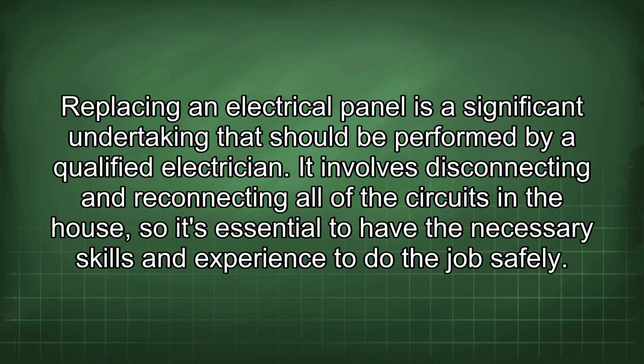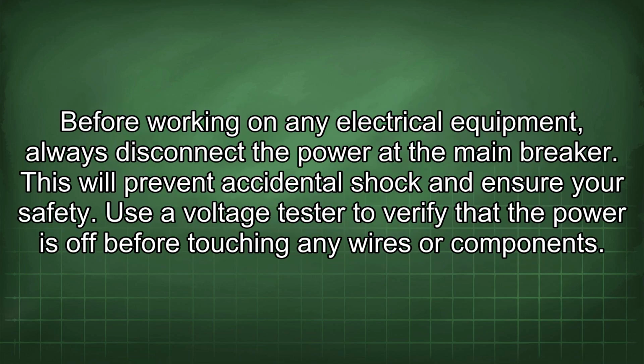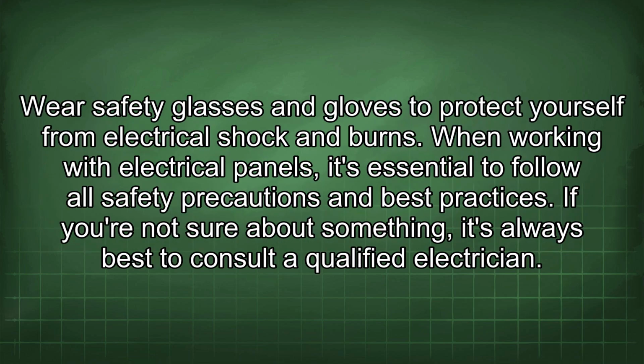It involves disconnecting and reconnecting all of the circuits in the house, so it's essential to have the necessary skills and experience to do the job safely. Before working on any electrical equipment, always disconnect the power at the main breaker. This will prevent accidental shock and ensure your safety. Use a voltage tester to verify that the power is off before touching any wires or components. Wear safety glasses and gloves to protect yourself from electrical shock and burns.